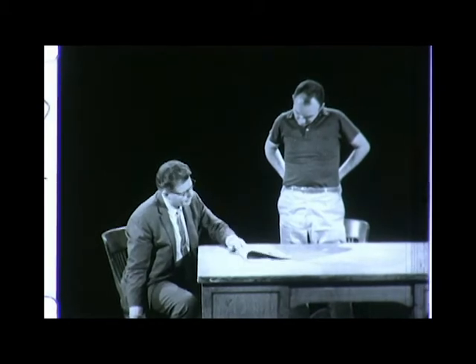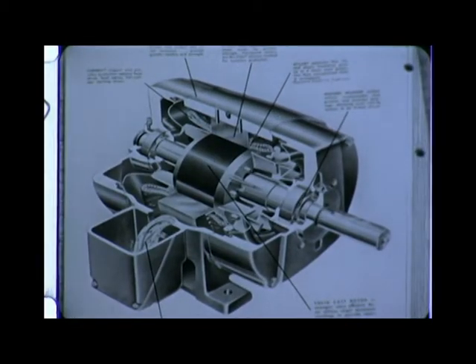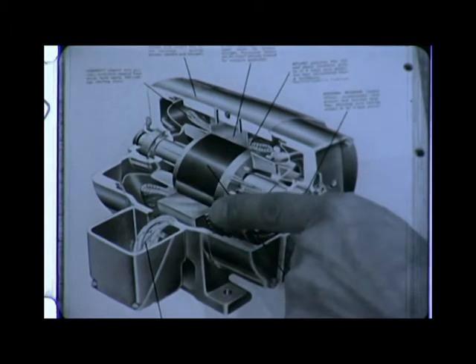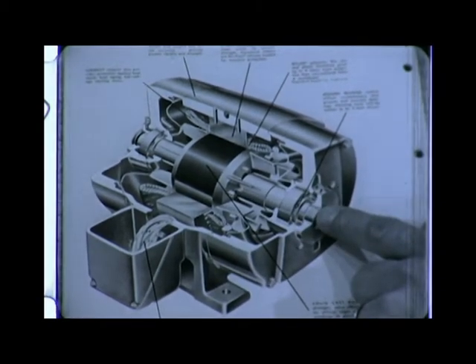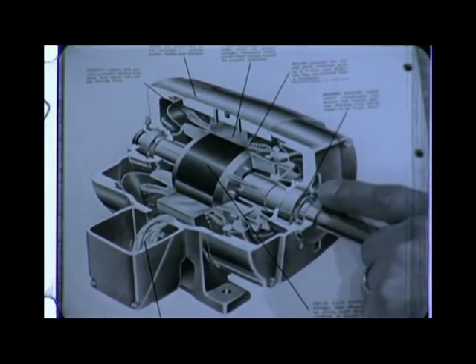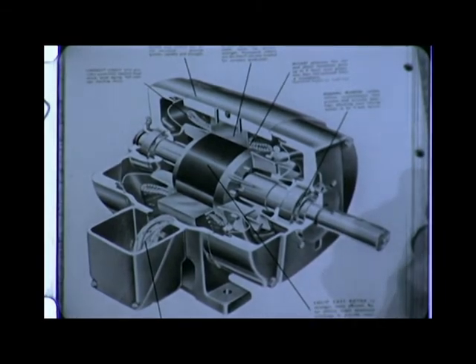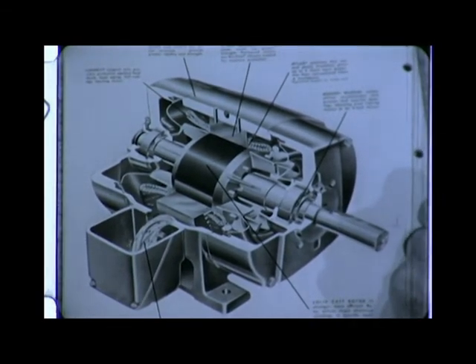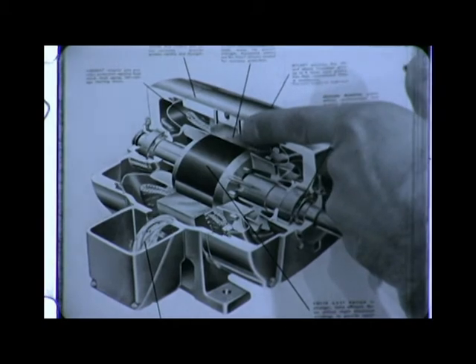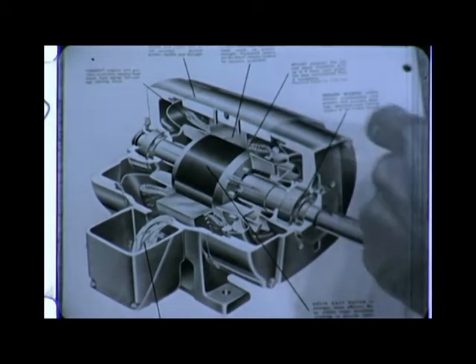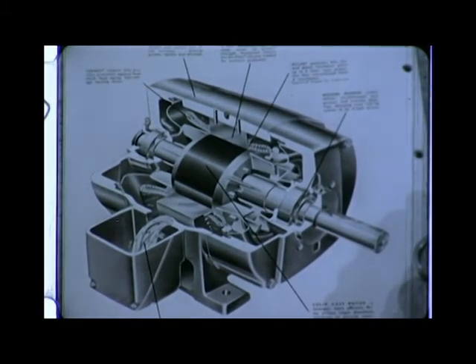Now, this is the inside of a standard motor. You can encapsulate the windings, but what about the bearings? If this abrasive dust gets into the bearings, you're in for trouble. Or worse yet, if the dust really gets thick, it could clog up the air gap between the rotor and the stator and cause a freeze-up. Don't forget, this clearance is less than a 16th of an inch in most motors.